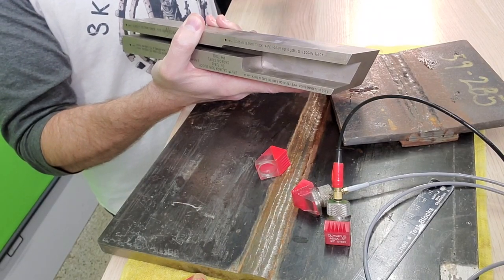And in UT, we're used to this plus or minus 2 decibel tolerance on our sensitivity, and you can see right away we're way beyond that. And just to prove that the surface finish on this is more representative of a real weld, we can run a quick transfer correction. I'll use the 3/8 inch step on the calibration block.